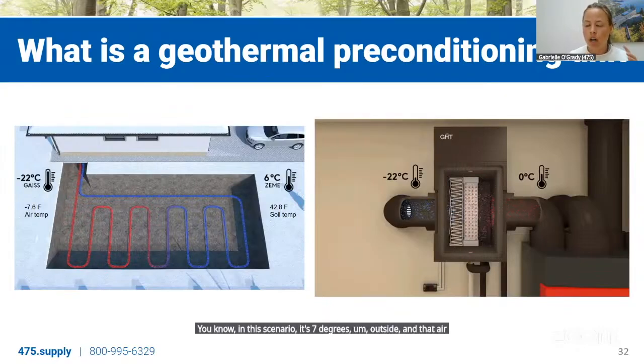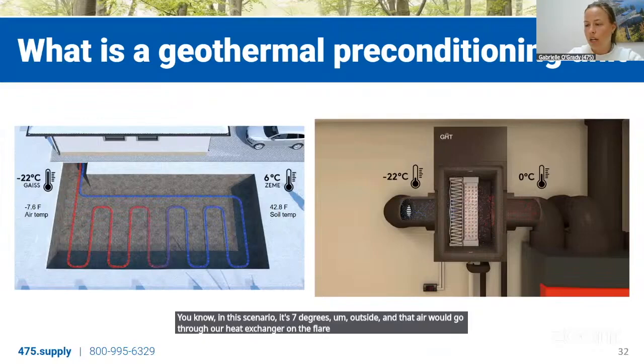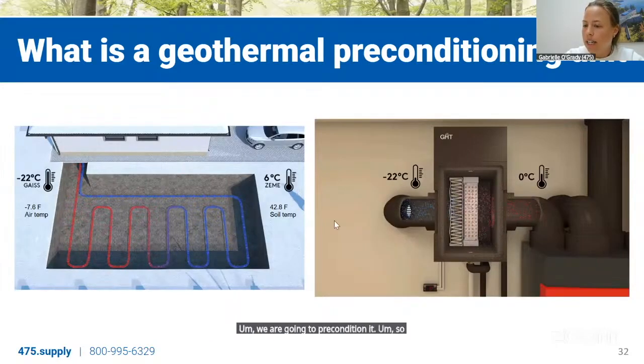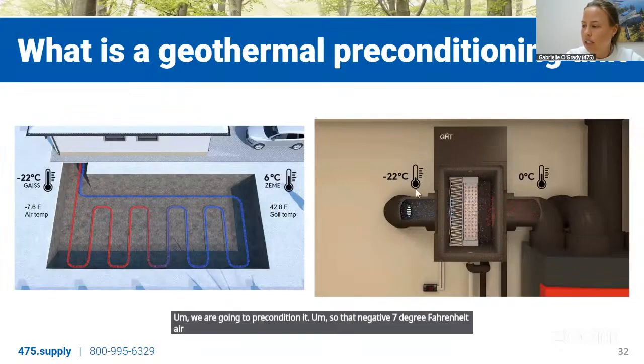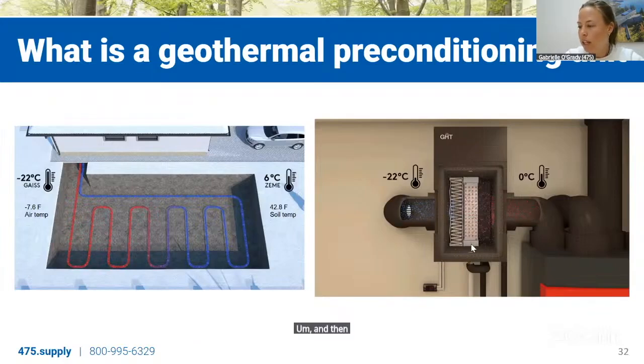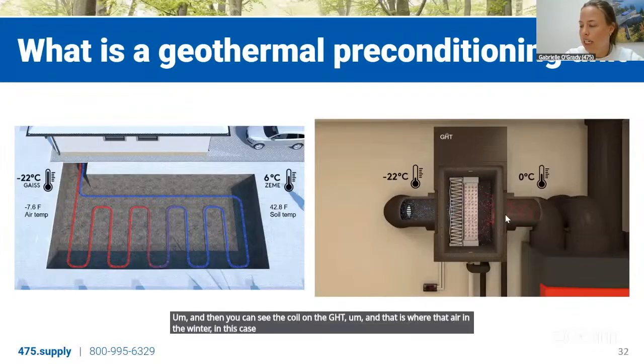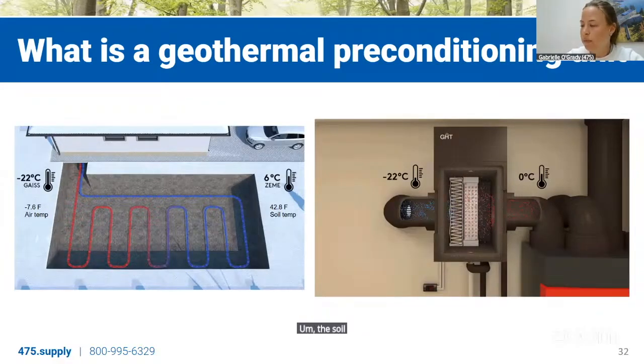In this scenario, it's -7 degrees outside, and that air would normally go through the heat exchanger on the FLAIR. But instead of bringing in that -7 degree air to heat exchange, we are going to precondition it. That -7 degree Fahrenheit air, as you can see on the left, goes through the GHT. There's a pre-filter before the coil, and then you can see the coil on the GHT. That is where the air in the winter, in this case, is heated using the heat from the soil to precondition it to no longer below freezing.